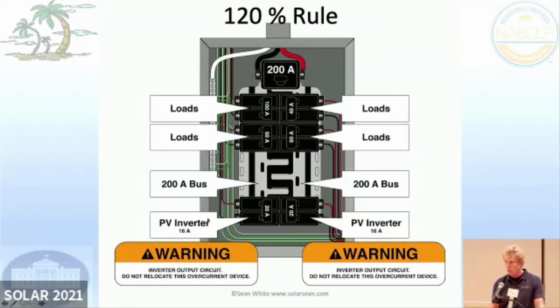A lot of times it is one breaker because you'll have somebody else owning the PV system and they need to monitor it very carefully, because the owner of the solar system, that could be somebody like Tesla or Sunrun, is going to carefully monitor that. And so they're going to put all the solar on a sub panel and then just feed it to one breaker. You'll oftentimes see stuff like that.